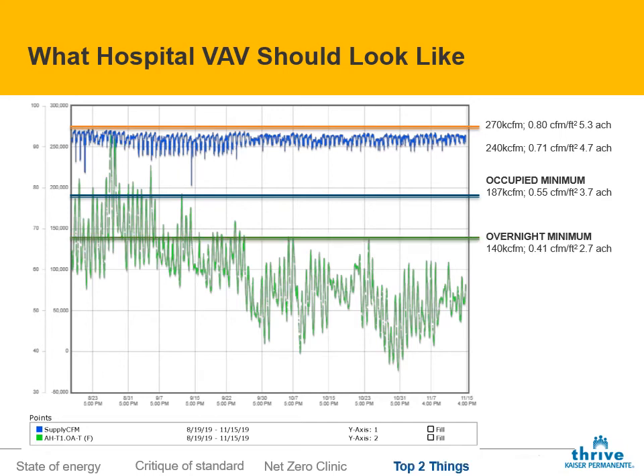The overnight code minimum drops down significantly. Some of these spaces can shut off, others can turn way down, but the overall code minimum at night should be about 0.4 CFM per square foot, which is more like 2.5 air changes for the volume of the building. That's still quite a bit of air. The ventilation minimum, generally driven by the exhaust, comes in at about 1.5 air changes for the volume of the building, or 0.23 to 0.25 CFM per square foot.